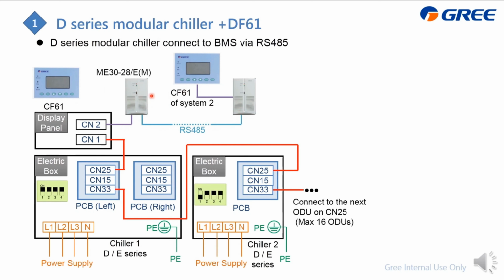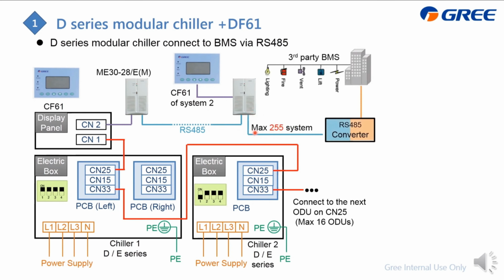In this case there are 2 systems, and this is system 2 from this CF61, which of course needs to connect to the chillers. The output from here can connect to a maximum of 255 systems, and just by going through this RS485 converter, you can connect to the PC, which is the BMS system.